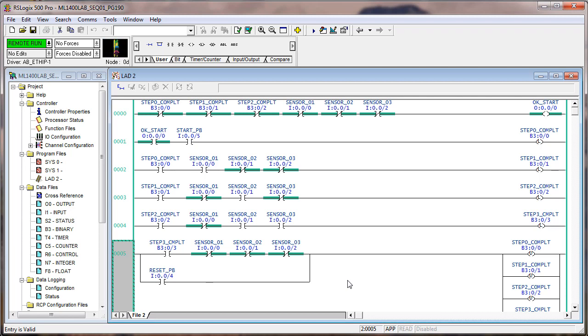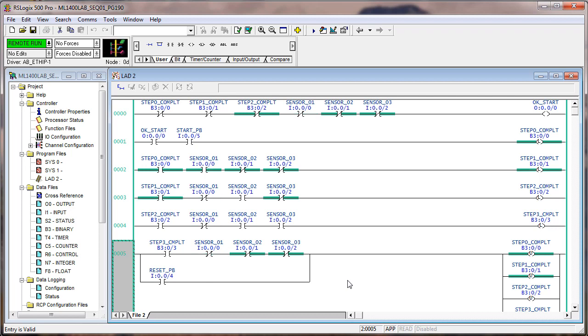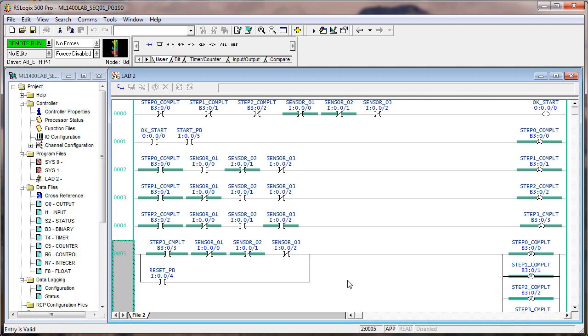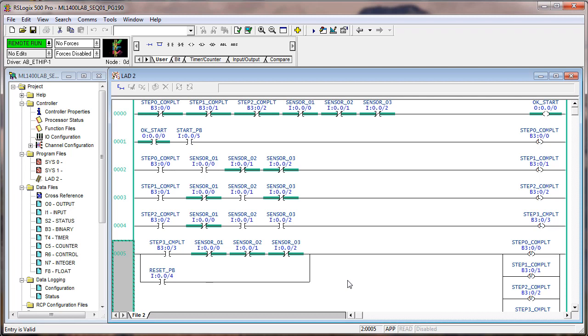This is okay, that step is complete, and then step one causes more motion that would pull the motion off of sensor one and onto sensor two. Now in the manual I talked about cartons traveling on a conveyor because that is much easier to visualize. And now we're simply waiting for something to arrive at sensor three. And again, that turns on some kind of an output device that causes motion that should pull back these sensors, and then it resets. It's back in the home position and ready to run another sequence.